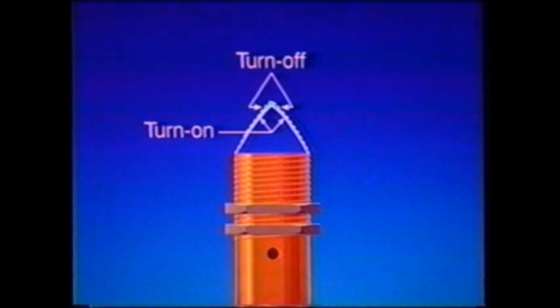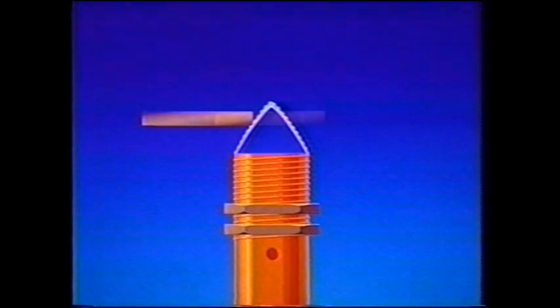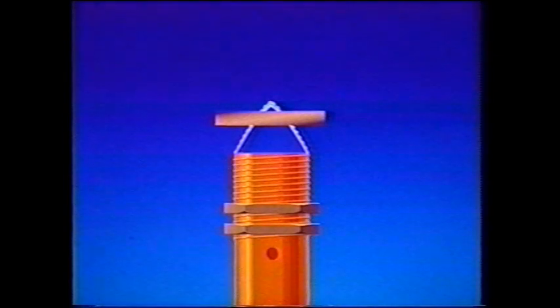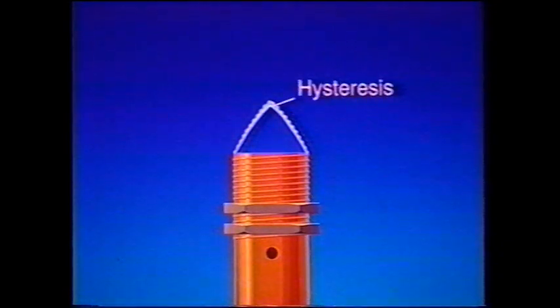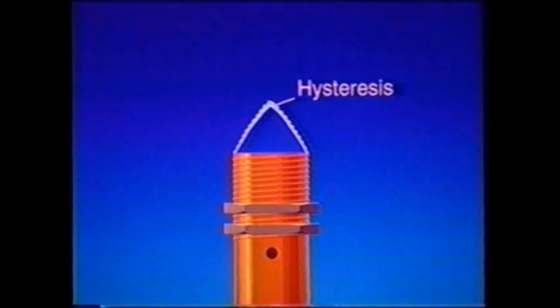Proximity switches have a specified nominal sensing range determined by a standard test procedure. Under these test conditions, a 30-millimeter cylindrical switch has a turn-on and turn-off graph. The inside solid line designates where the switch will turn on as the target approaches. The outside broken line shows where the switch will turn off as the target passes the switch. The difference between turn-on and turn-off, or hysteresis, provides stable operation by preventing the switch from chattering between the on and off states.